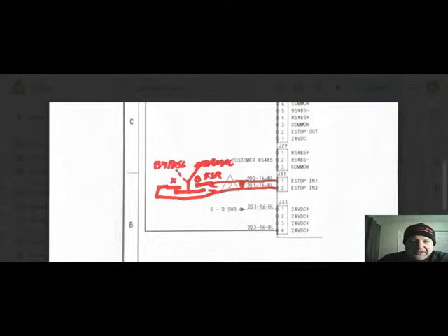Again, this would be just a little 2-position switch. Cut it into the door, mount it on the wall, wherever you want to put it. Doesn't necessarily have to be even local to the compressor room. This could be something that's tied into the DCS or the building automation system or something like that, where the operator hits a bypass button on their screen, and then it just maintains this latch while the fire suppression system is doing what it's doing, and it doesn't interrupt the compressor.